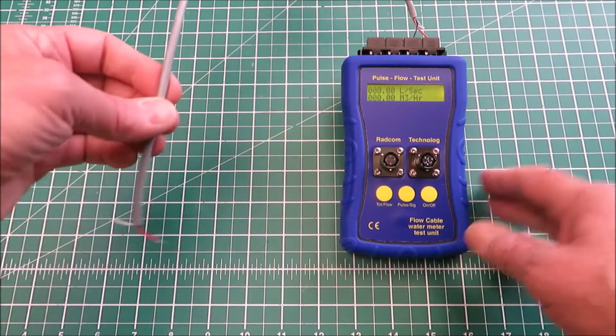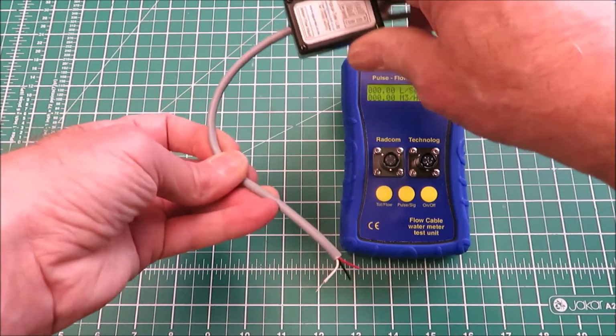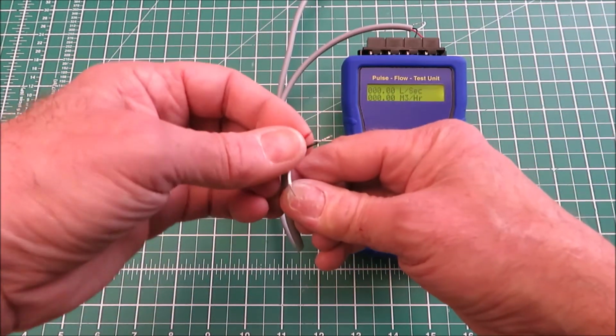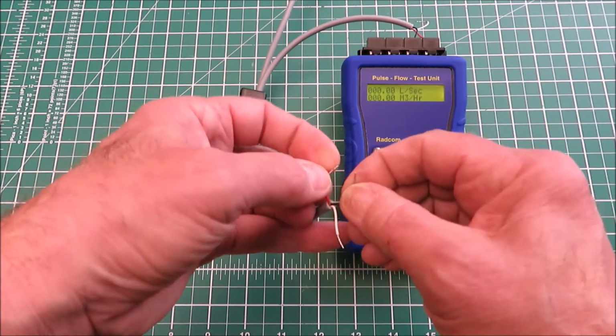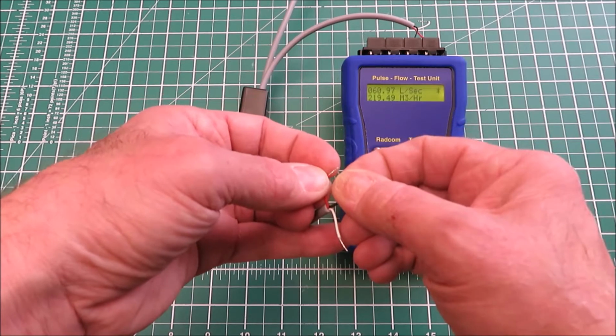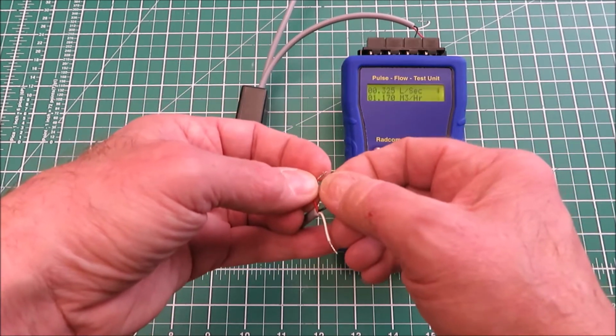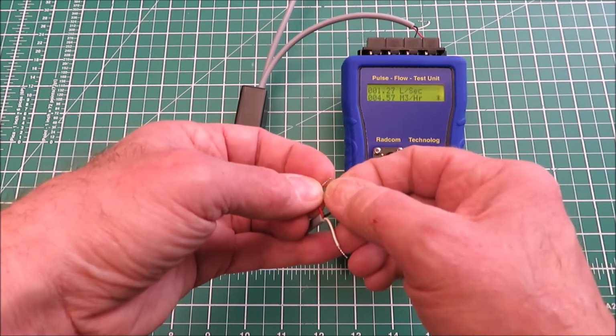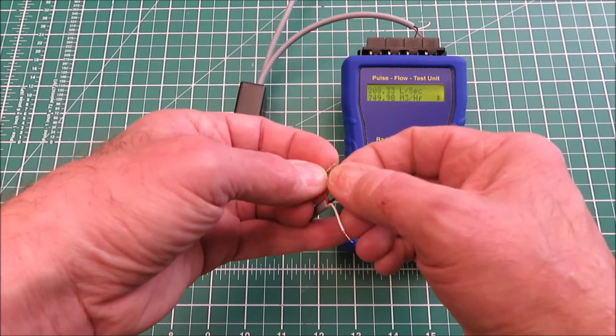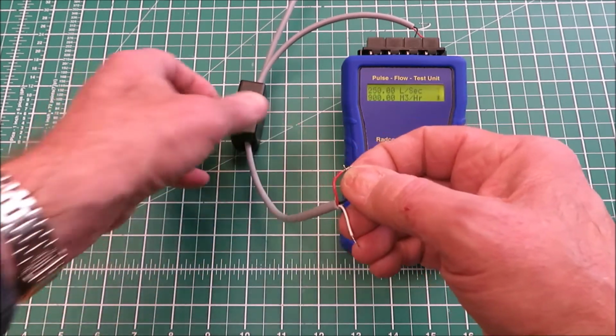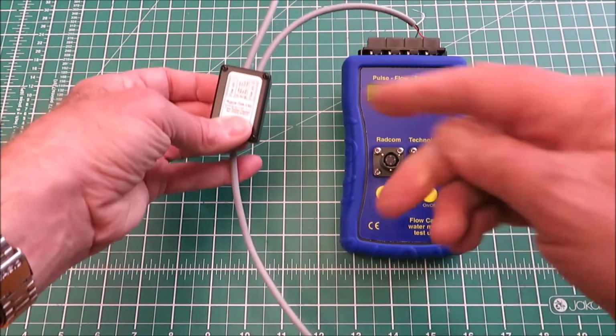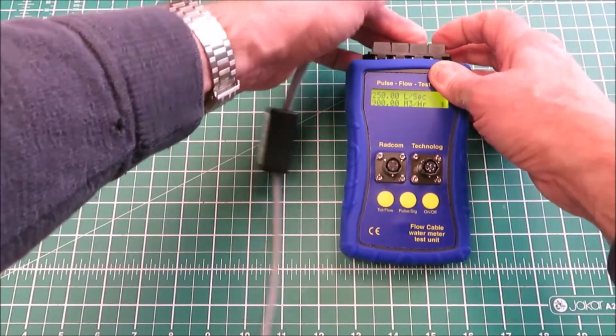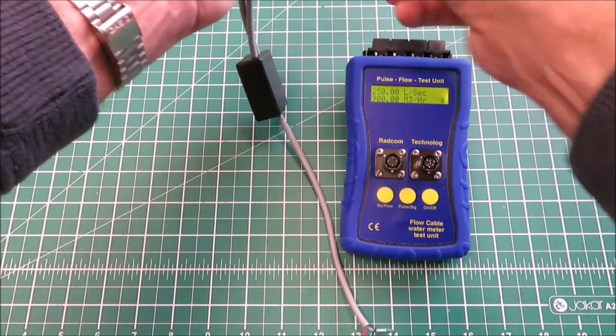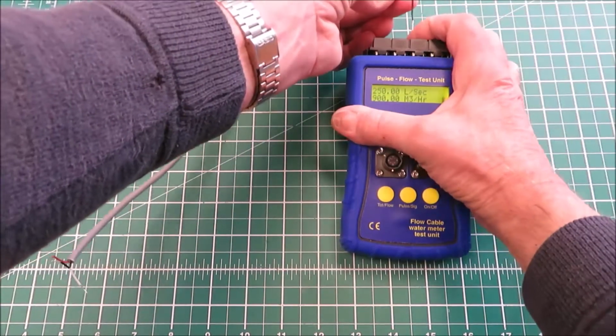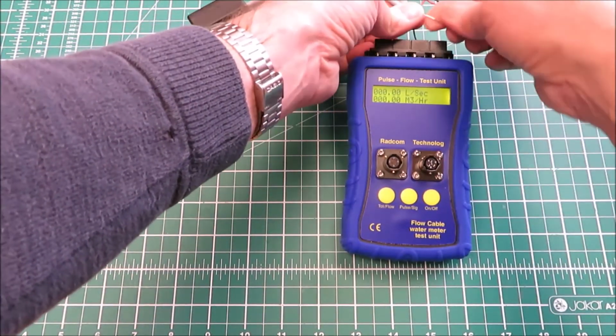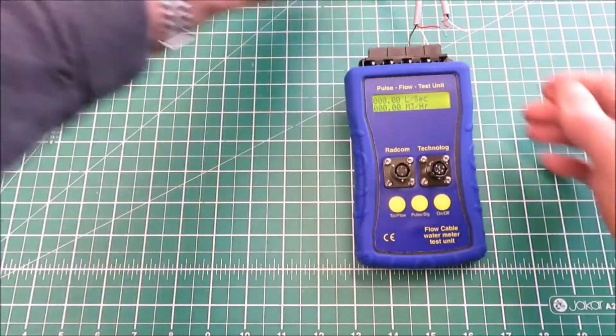So now that I've got it connected, one of the things that I can do is get hold of the black and red wires there, and if I just touch them together, keep touching them intermittently, you can see that the pulse test unit thinks it can see a flow, and that is one way of simulating a flow into the splitter. And we've actually just proved that one leg out of the splitter is working. If I want to do that with the other leg, I just take that out, swap it over, or I could even swap it to the white wire. I'll swap it to the white wire on this occasion, so that would be the other flow channel.